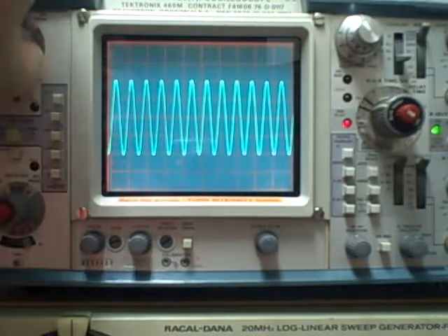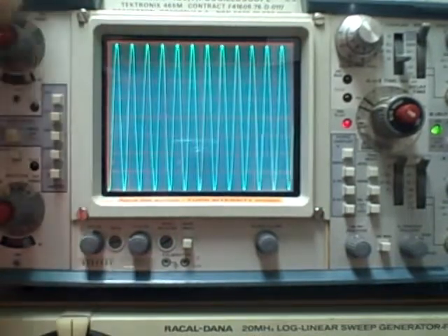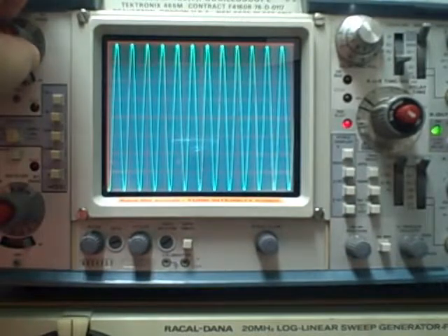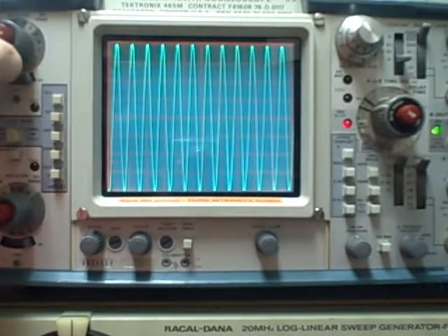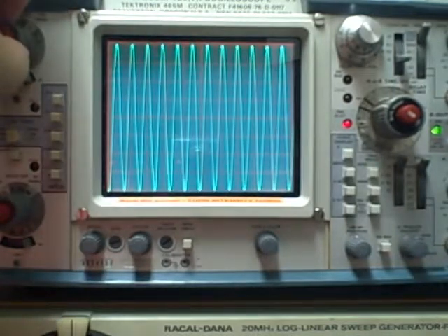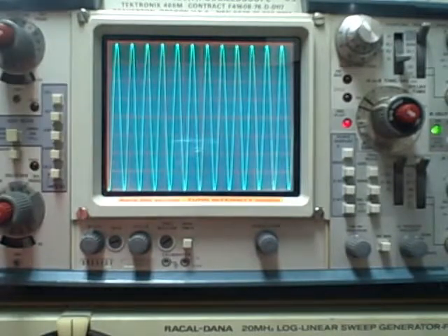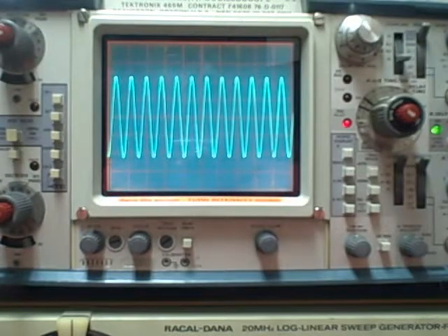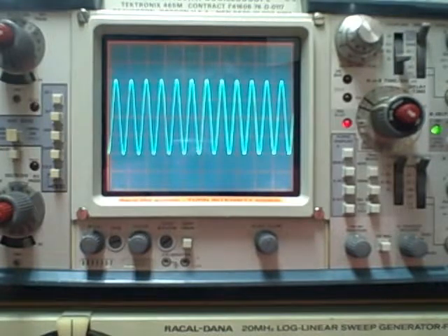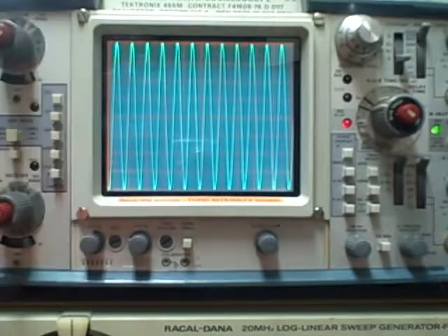If I go to 10 millivolts per division, we should be full. We are. And if I go to half scale on this, then I need to be at 20 millivolts. That'd be 14.14214. We're at half scale. If I go to the final range for full scale, we're done with channel 1.